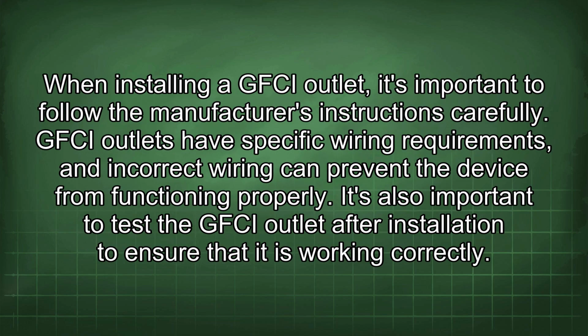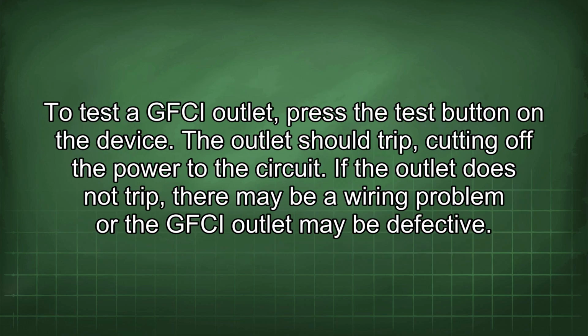When installing a GFCI outlet, it's important to follow the manufacturer's instructions carefully. GFCI outlets have specific wiring requirements, and incorrect wiring can prevent the device from functioning properly. It's also important to test the GFCI outlet after installation to ensure that it is working correctly. To test a GFCI outlet, press the test button on the device. The outlet should trip, cutting off the power to the circuit. If the outlet does not trip, there may be a wiring problem or the GFCI outlet may be defective.